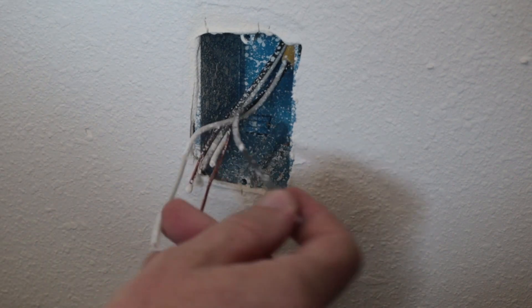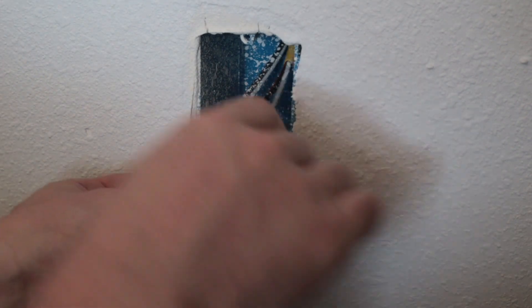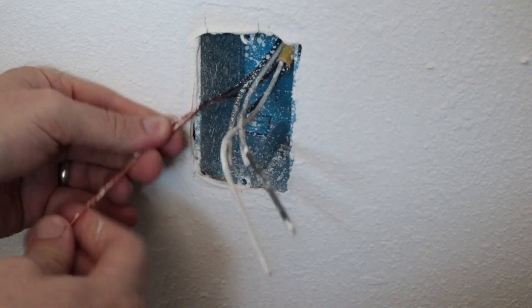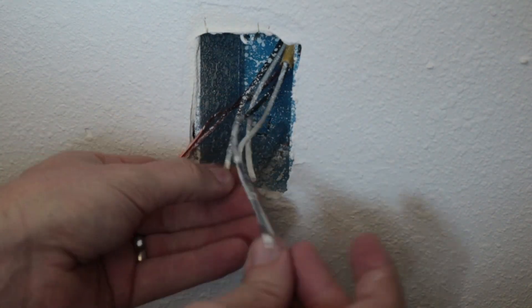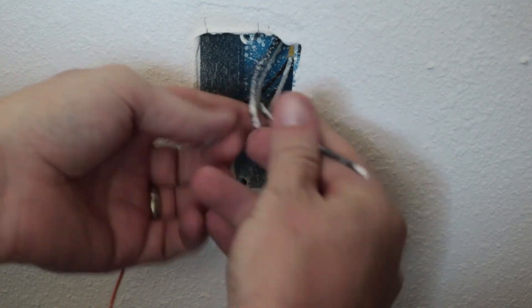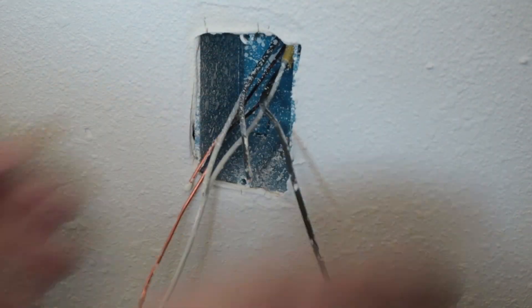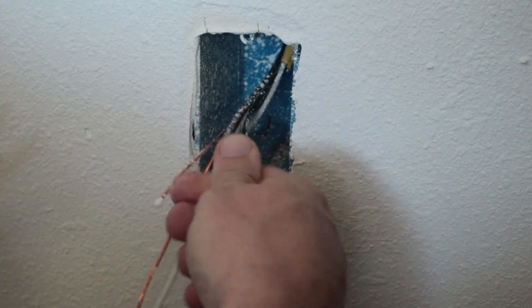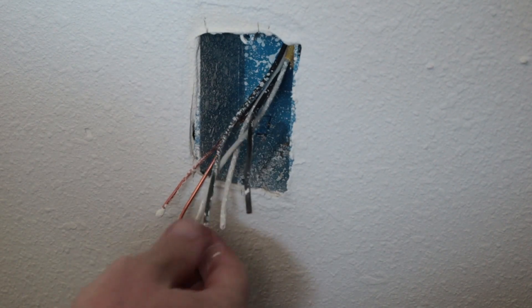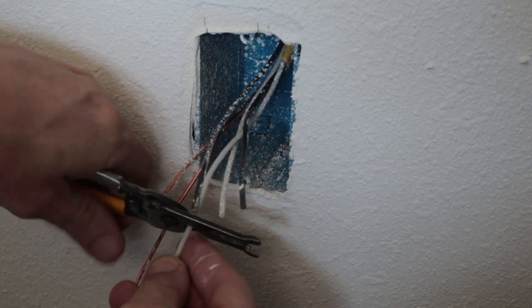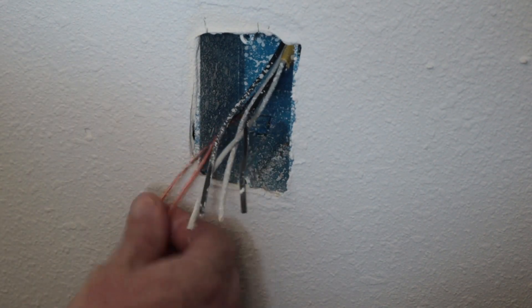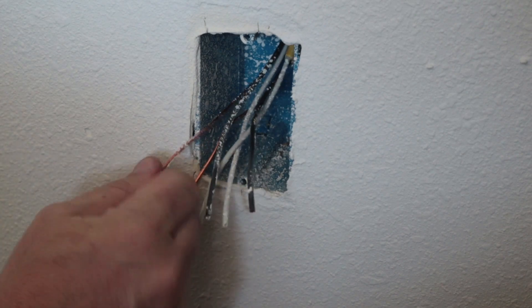The next thing we're going to do is go ahead and separate out our wires. So we have the grounds, the one without insulation on the left side. The black wires will move to the right side and the white wires we'll put in the middle. These are almost a little bit too short. You want to cut it so it's about six inches coming out of the top of the box. So I'll cut these to length. And that one's okay actually how it is.